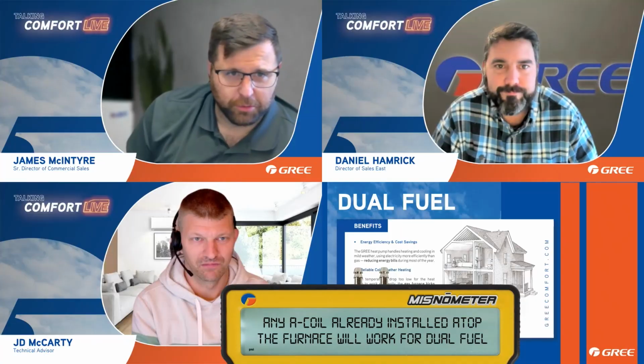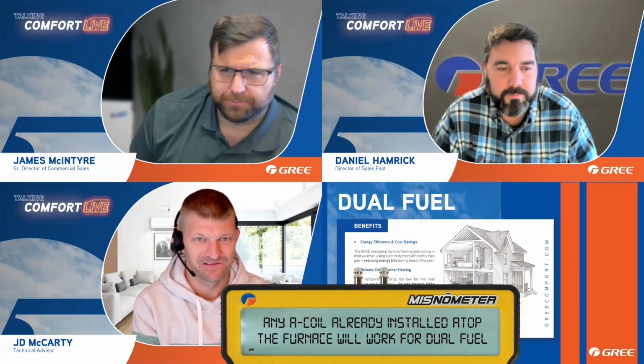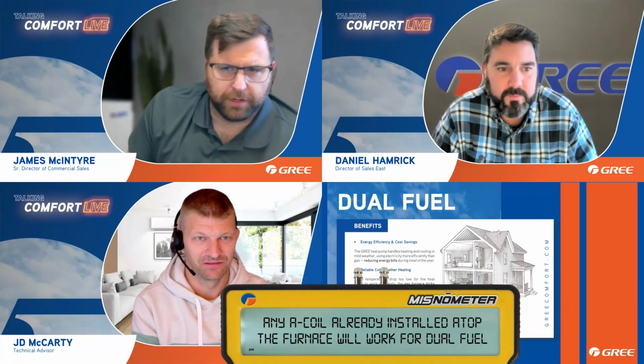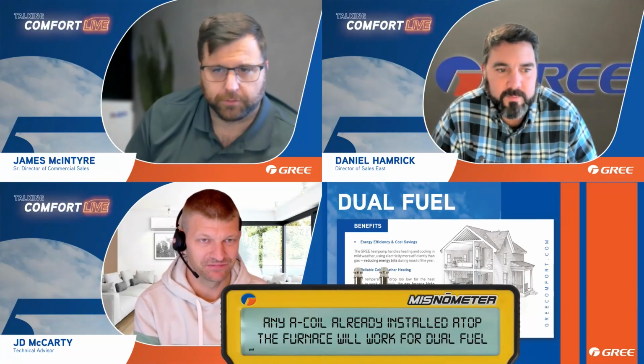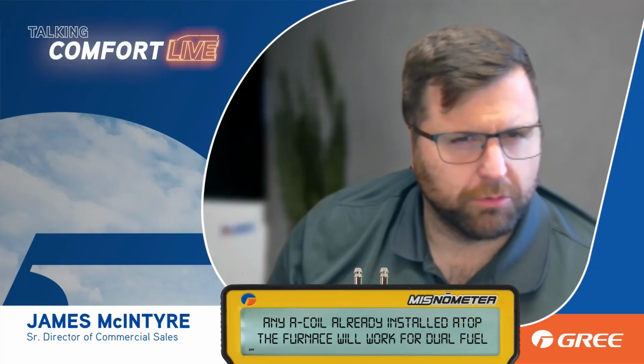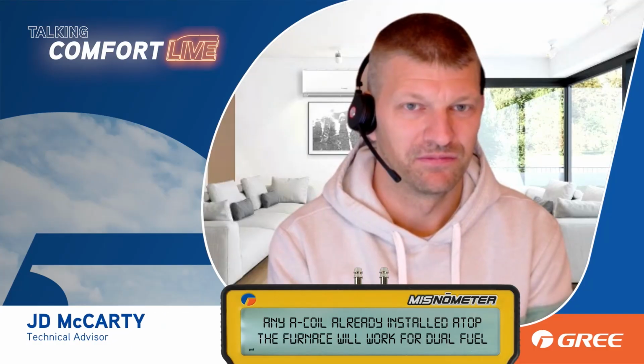I believe that is a misnomer, right? Certainly. Only A-coils with the proper metering device can work with a heat pump in a dual fuel scenario. For GREE systems, with our A-coil, it's an electronic expansion valve. If you're using the wrong metering device, the heat pump won't operate correctly in heating or cooling mode. You'll likely experience poor performance, high head pressure, or other system faults. So if you had a non-bleed, what was that again on the TXVs? It's been a while since I talked TXVs. Yeah, bleed or bypass. You got to have that. I mean, you need a heat pump coil.